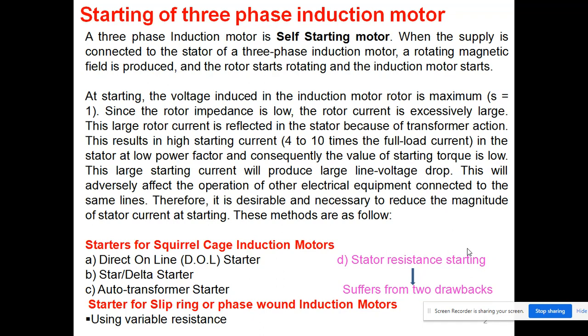This large starting current will produce a large line voltage drop, and this will adversely affect the operation of other electrical equipment connected to the same line. Therefore, it is desirable and necessary to reduce the magnitude of stator current at starting. For that purpose, we use starters. What methods do we use to reduce this stator current at starting? For a squirrel cage induction motor, yesterday I mentioned only three methods: direct online starter, star delta starter, auto transformer starter.